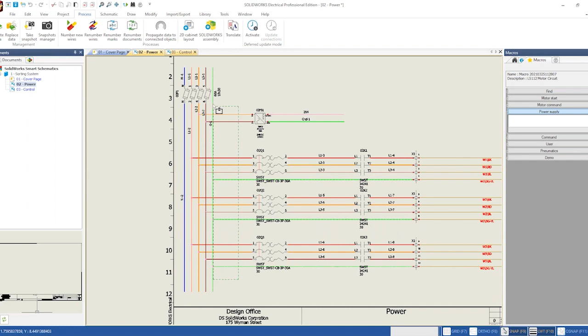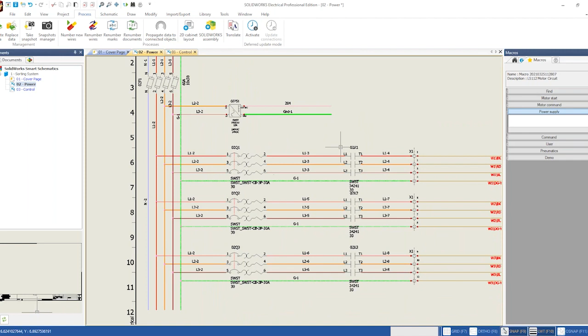Now, you may notice there's no wire numbers being listed right here, and that's because we have what's called equipotential numbering turned on. So anything with the same technical voltage potential is going to be displayed as the same wire number. So L1-2 is the same as L1-2 down here, and that's just a setting within the application to show that information.